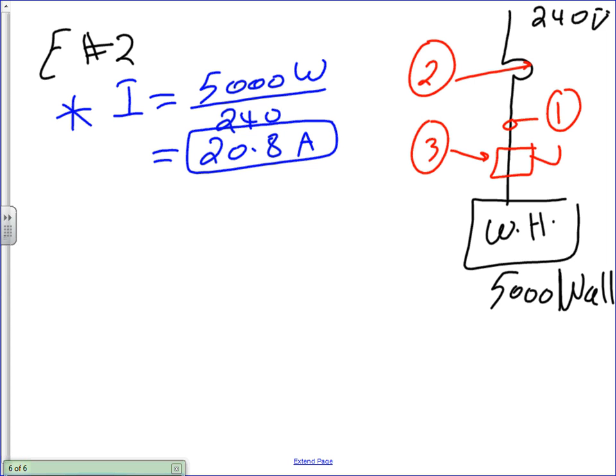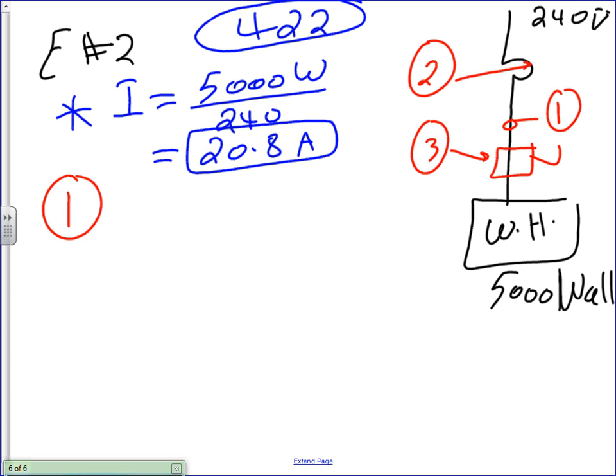Now, a water heater is not a pump. It's not a motor. So we don't apply the rules of a motor on it. It's an appliance. With appliances, guys, they're continuous loads. So we size them based on 125%. So we are in Article 422. That's the article that applies for appliances. The first thing I'm going to size there, one, branch circuits. This is called branch circuit, basically conductors. 1.25 times 20.8.